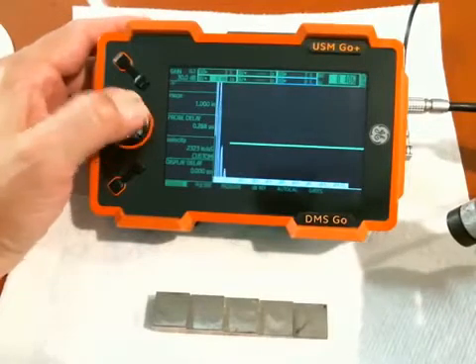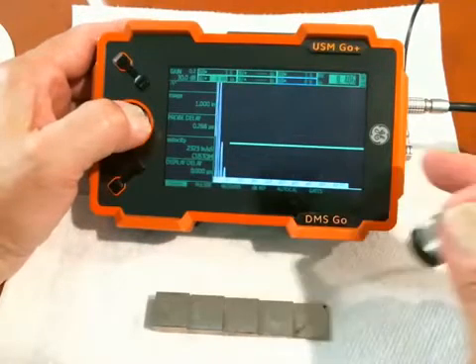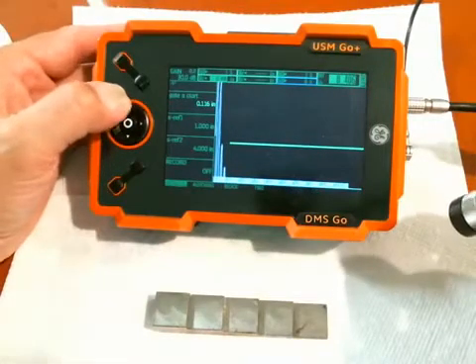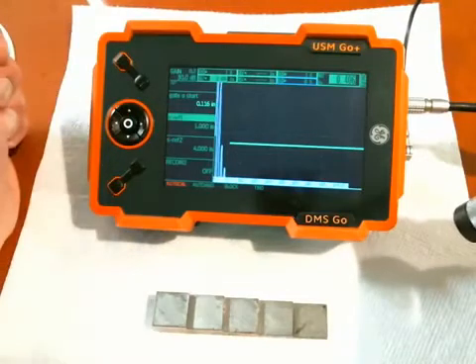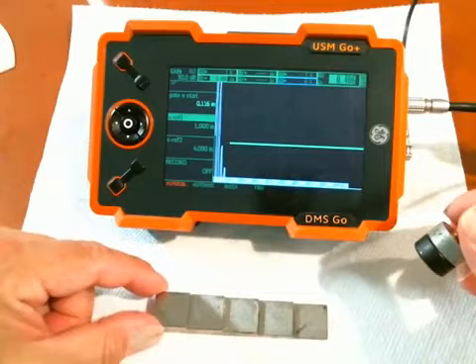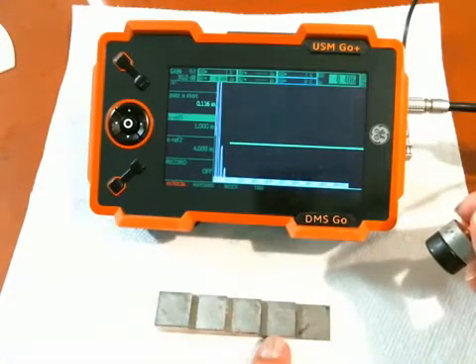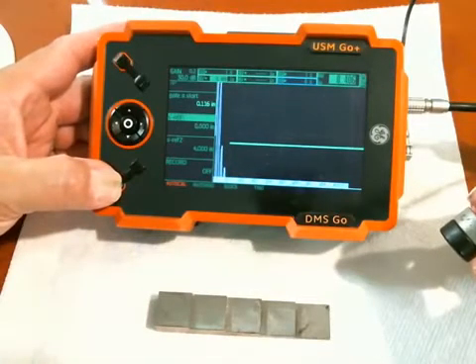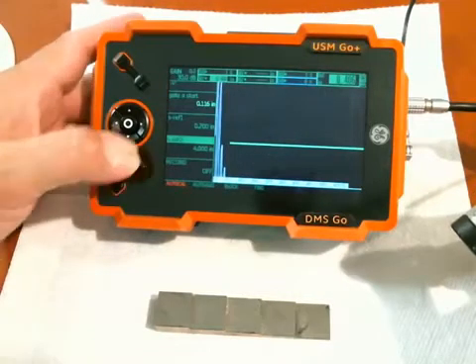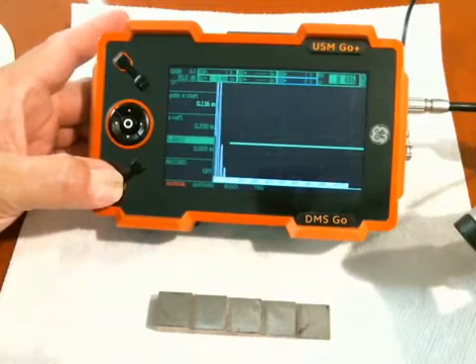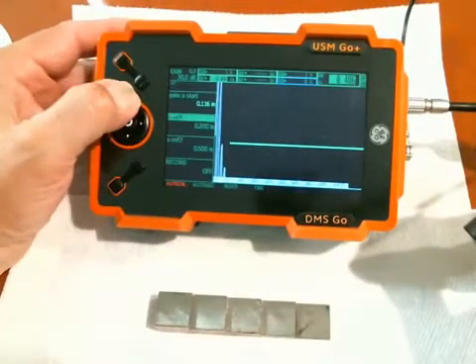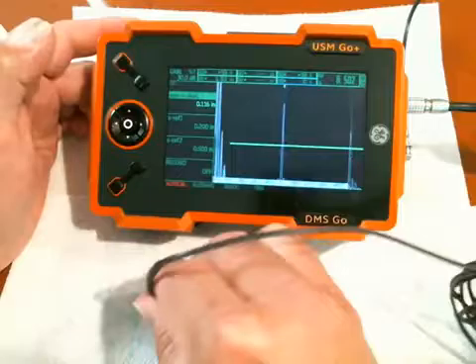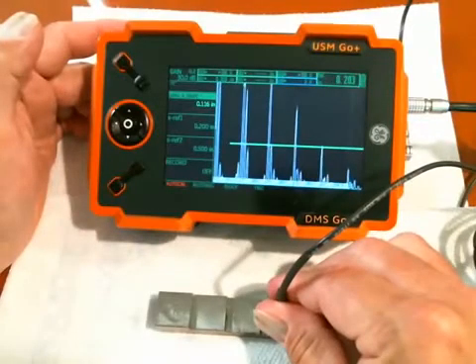The process of adjusting probe delay and velocity until we get calibrated on two thickness points can be a little inconvenient and time-consuming. So we've provided an AutoCal feature. There's an AutoCal menu. It's going to ask me for two reference thickness points — we're going to do a two-point thickness calibration. I have my block here; I'll tell it that my thin reference is 0.2 inch and my thick reference is 0.5 inch. SREF1 for F1 is my thin, adjusted to 0.2. SREF2 for F2 is my thick, adjusted to 0.5. I've already positioned gate A to a convenient place, giving me a nice long gate that starts early enough to see echoes from both steps.